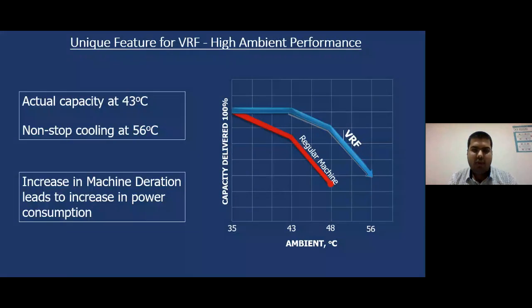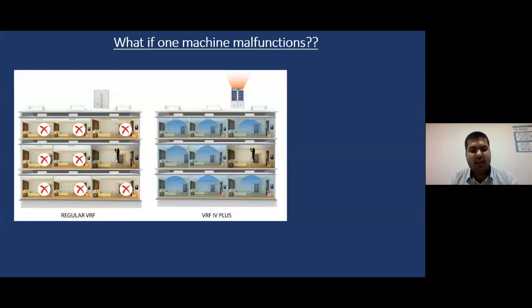There's a basic question which comes up for VRF. What if my one machine malfunctions? What if all the systems are connected together? What would happen if my one IDU or my one ODU does not work? In the case of a regular machine, if one unit has to be serviced or one machine goes wrong, all my other machines go for a toss. My entire circuit breaks down. But in the case of VRF, there's a function called IDU isolation function. I can separate that IDU from all the other indoor units, and my entire system can work just fine.